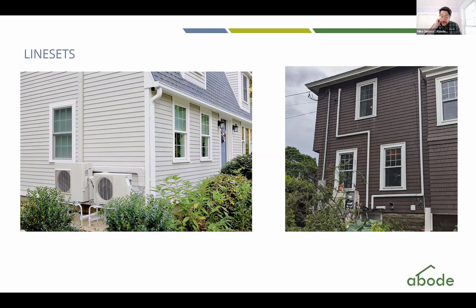Yeah, most of the time if you can run the line sets inside the house, you should. One thing I didn't mention is condensate—when these systems run as an AC, one byproduct is moisture, which needs to be drained out. It's easier to drain the moisture outside the house than down in the basement if there's not already a laundry or sink down there. So that can require a little extra attention to detail, just making sure there's a solution for getting all the condensate out. But there's nothing wrong with running the line sets inside the house.